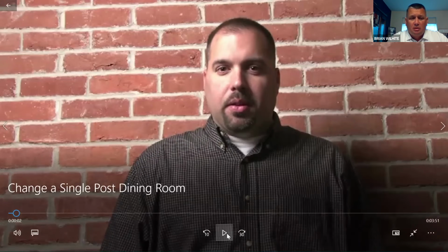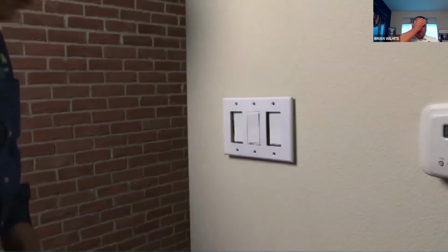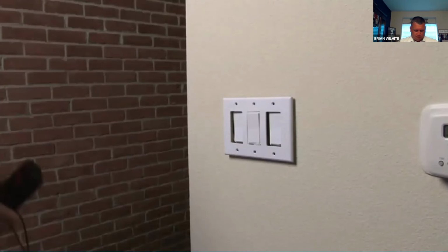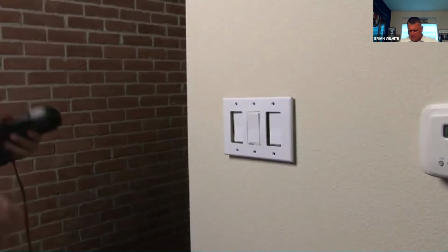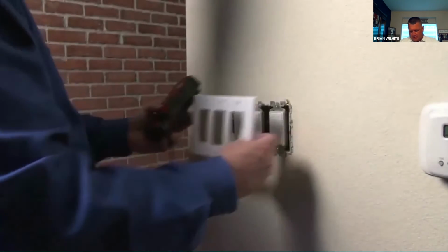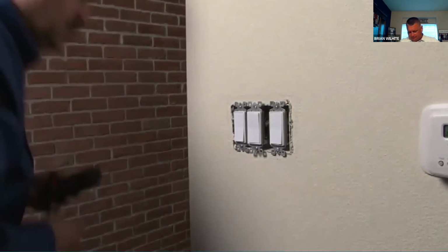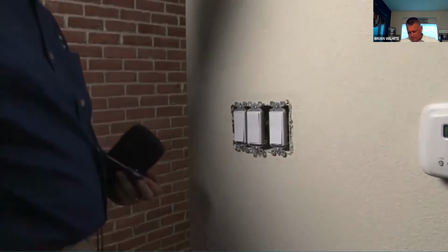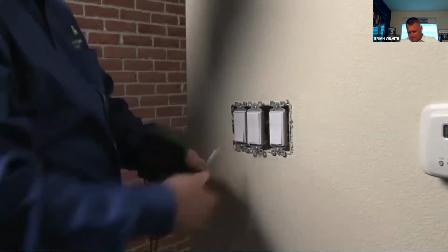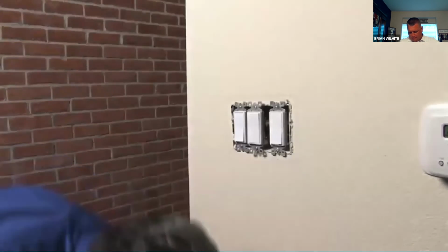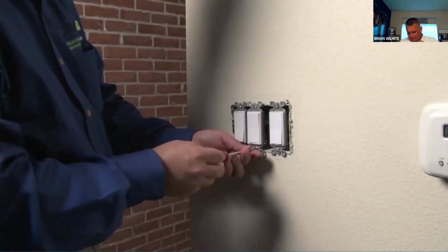We received a call from residents stating that they're... Can you guys see that screen? Yeah. The dining room light fixture is not working, so we're going to send a technician out there to diagnose the problem. Our technician is going to troubleshoot the call for the dining room light not working. Our technician goes ahead and removes the cover plate. Go ahead and take off the switch, removing the 2 screws.